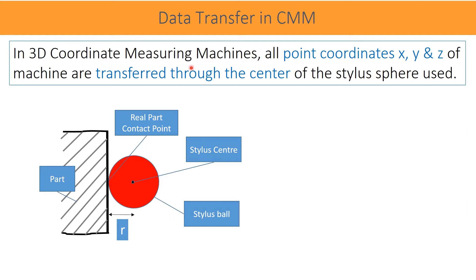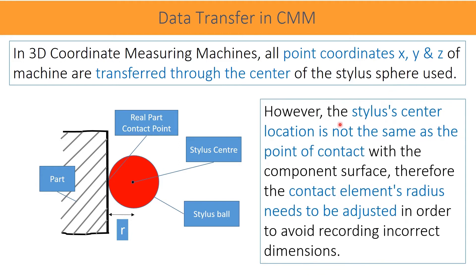In all 3D coordinate measuring machines, point coordinates which are read from the machine scales X, Y, Z are transferred from the center of the stylus sphere or diameter. However, the stylus center location is not the same as the point of contact with the component surface. Therefore, the contact element's radius needs to be adjusted in order to avoid recording incorrect dimensions.